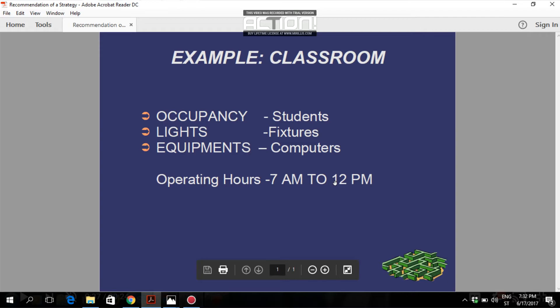After 12 o'clock the class will be empty. We can assume there won't be any lights on, no one will work on the personal computers, and there will be no human presence — meaning occupancy will be zero. So we have to make three different profiles: occupancy for five hours, light fixtures on for five hours, and equipment operating for five hours. HAP will then calculate the heat load due to these three components during their operation.